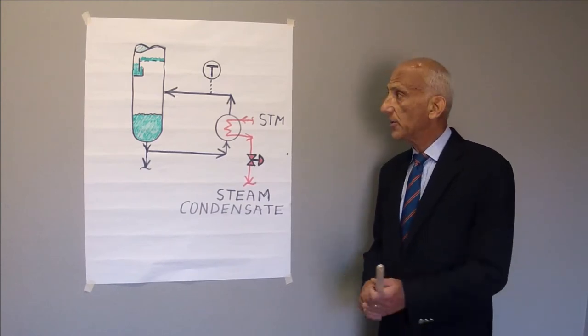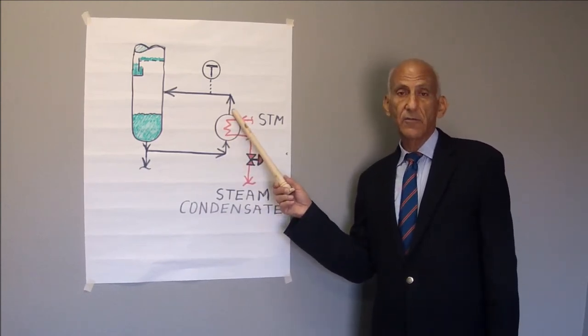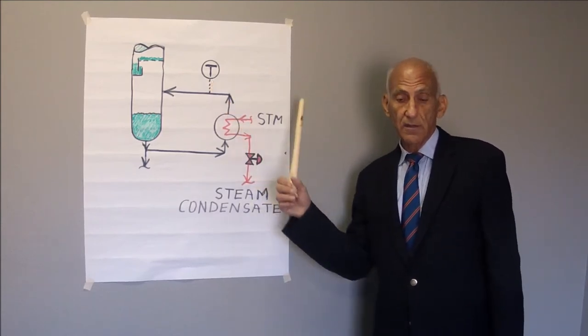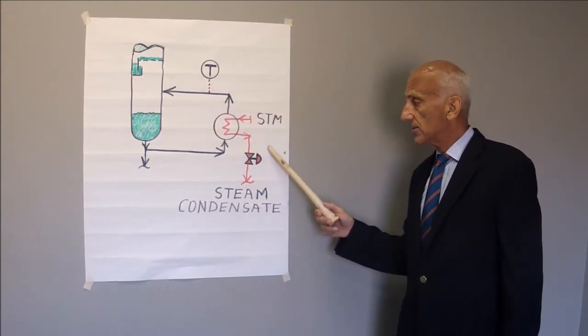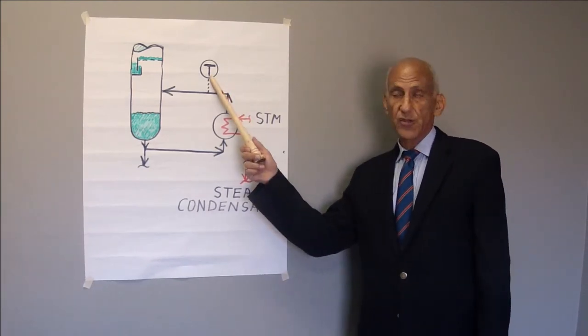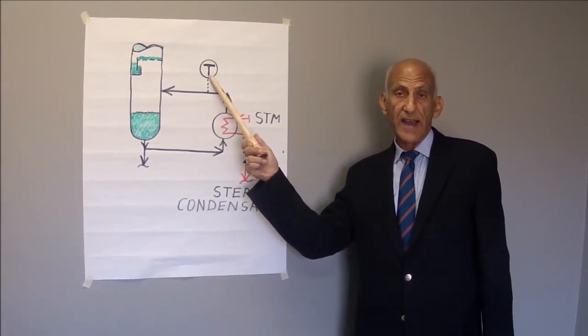And the way I do it is I simply look at the reboiler shell side outlet temperature at T1, and I adjust this control valve to try to maximize the temperature on the process side on the outlet of the reboiler.